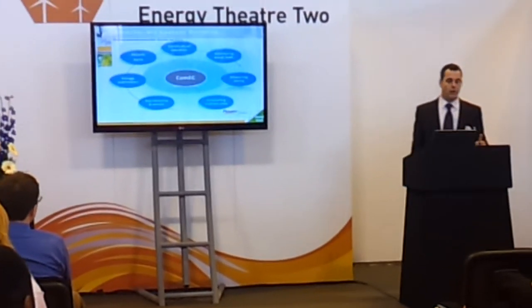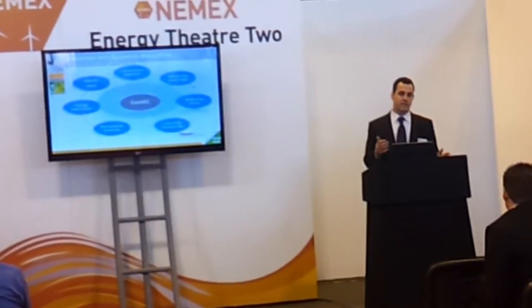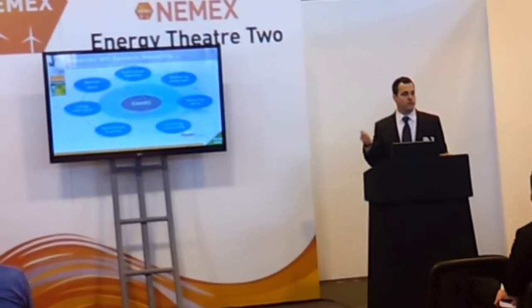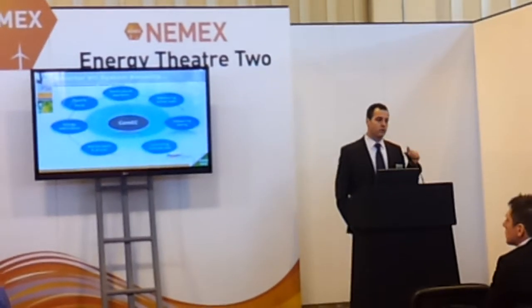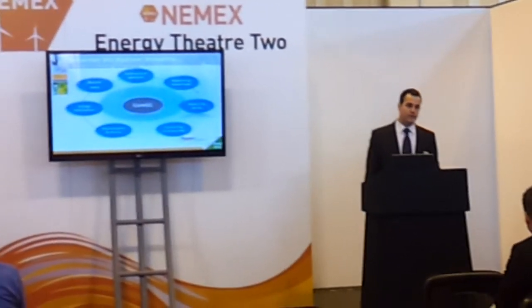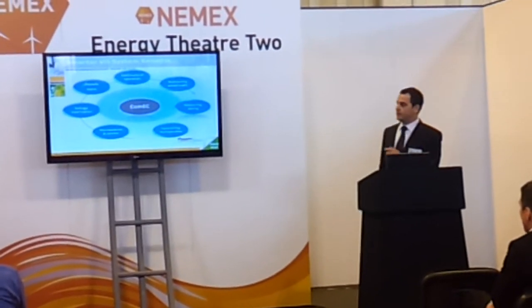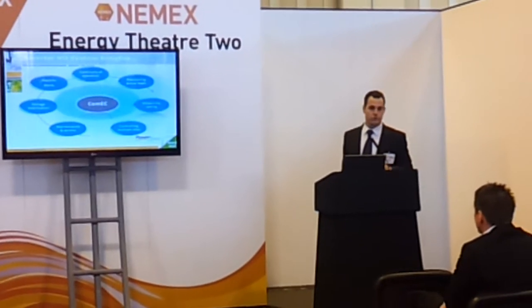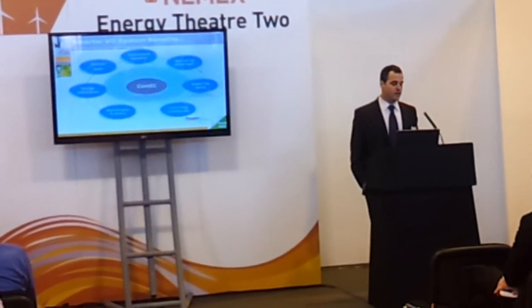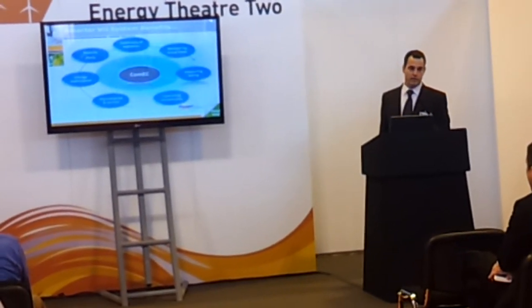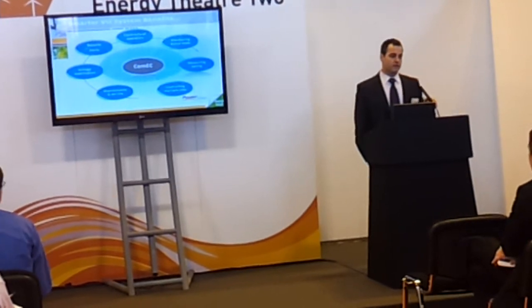The system gives you the means to control and configure your sites remotely. You can configure and change the voltage output on a site remotely. You can monitor the changes as they happen, monitor all operational parameters, and see not only how the load changes but how temperatures are changing and whether there are events of missing phase, overload, over-temperature, and so on. Everything is displayed in real time, data-logged with the accuracy of a data logger, and can be generated into reports and proactive alerts for operators.